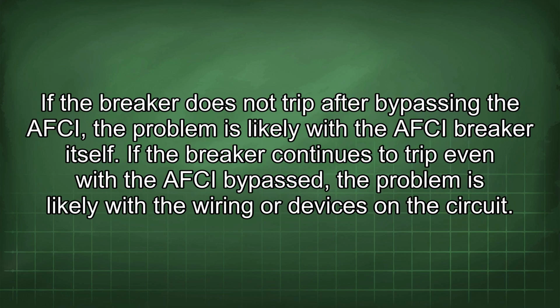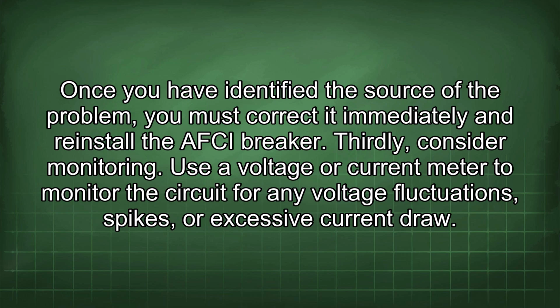If the breaker does not trip after bypassing the AFCI, the problem is likely with the AFCI breaker itself. If the breaker continues to trip even with the AFCI bypassed, the problem is likely with the wiring or devices in the circuit. Once you have identified the source of the problem, you must correct it immediately and reinstall the AFCI breaker. Thirdly, consider monitoring.